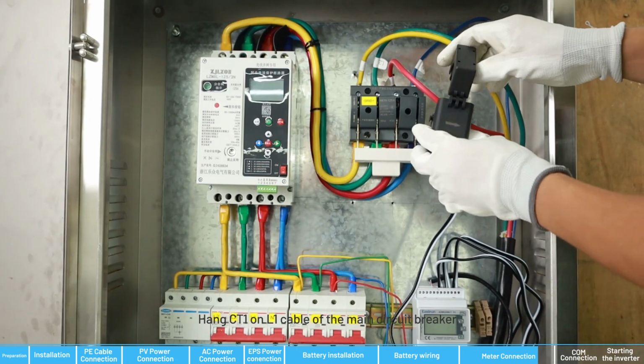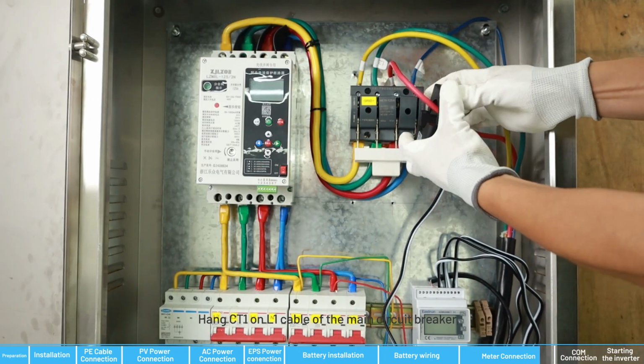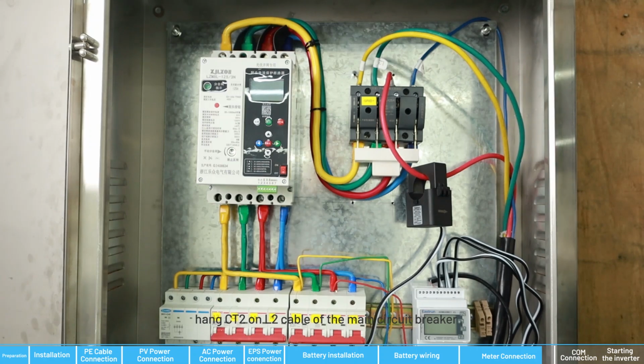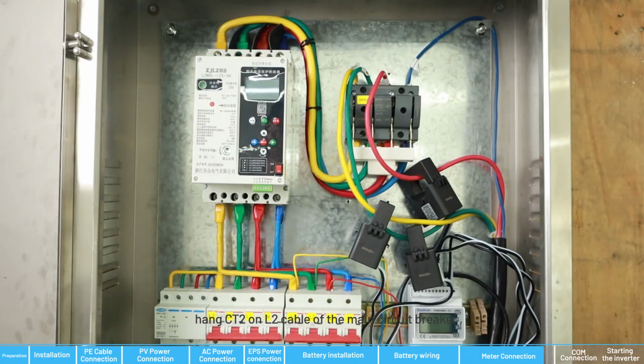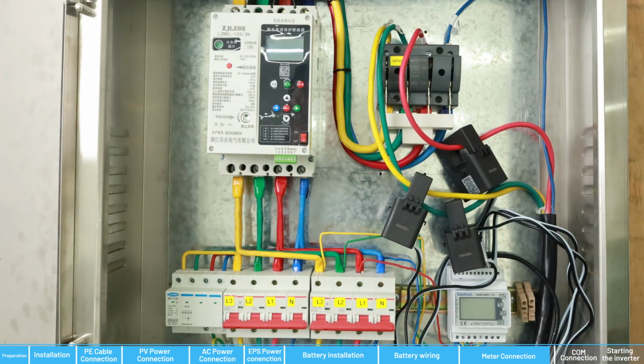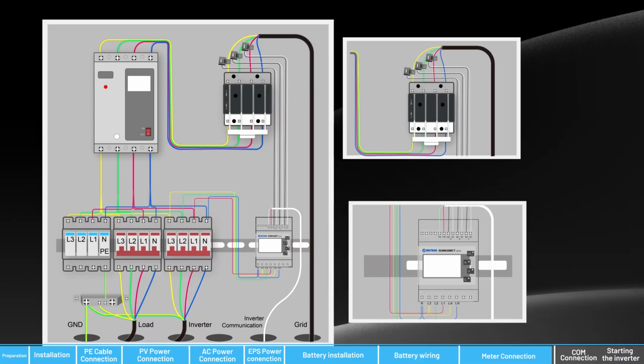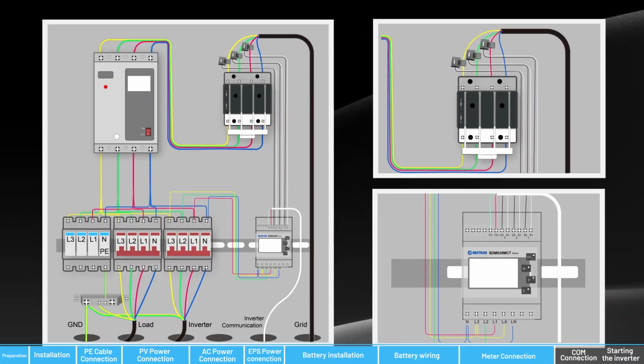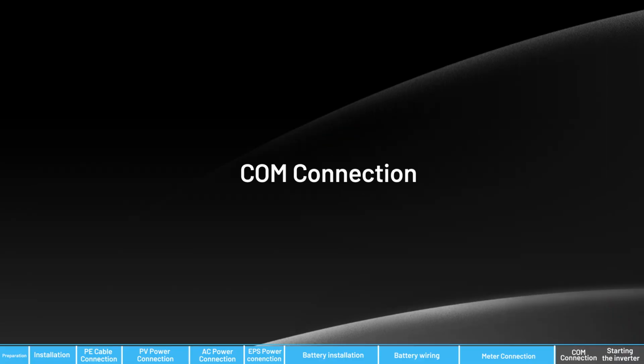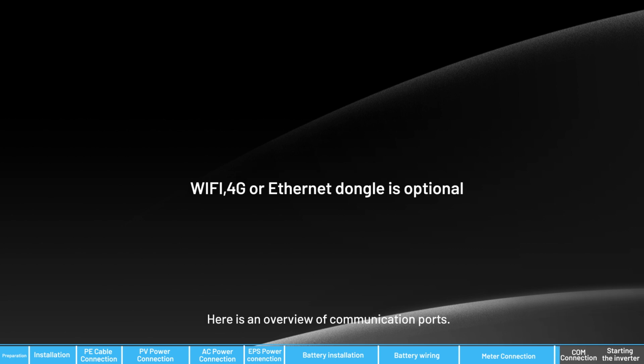Hang CT1 on L1 cable of the main circuit breaker. Hang CT2 on L2 cable of the main circuit breaker. Hang CT3 on L3 cable of the main circuit breaker. Here is an overview of communication ports.